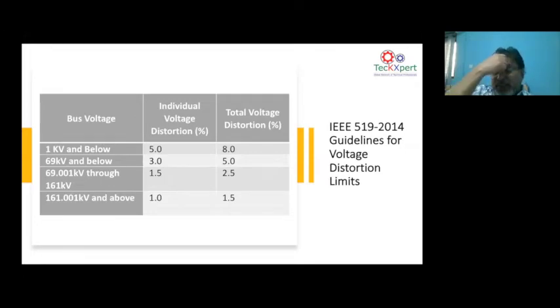When it comes to IEEE 519, yes, there are stipulations in terms of what harmonic is permitted in low voltage. The total harmonic voltage distortion is 8%. Individually it is 5% for low voltage. As you go to the higher voltages, you have reduced distortions.